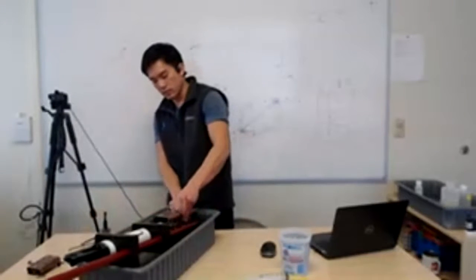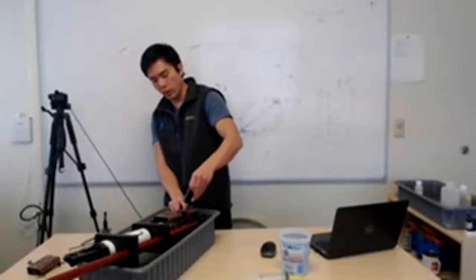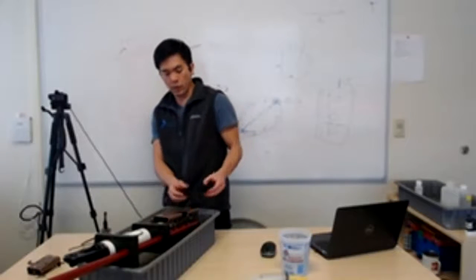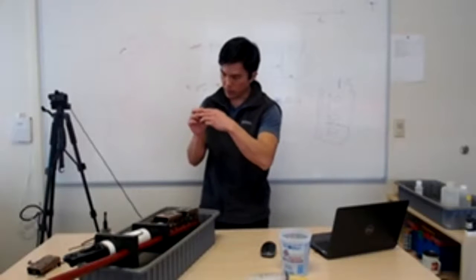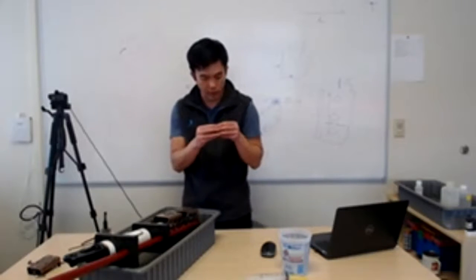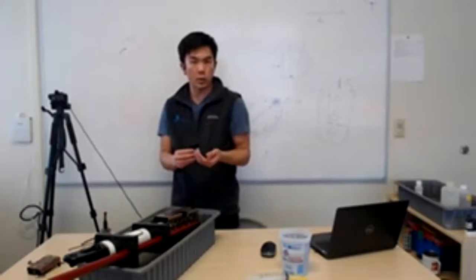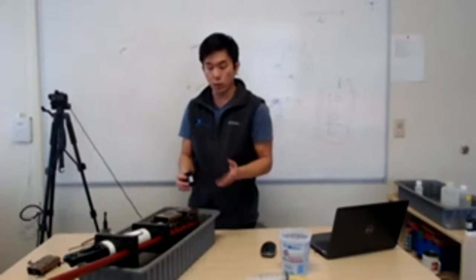And then take the sensor, pull it straight out, shake off any water, and take a moment to inspect it. It actually did pretty good this time, so there's not really any water around the connector, but if there were any water on the connector or the pins, that's going to be the clean DI water we just flushed through the system. Now I'm safe to put this back into the soaker block.